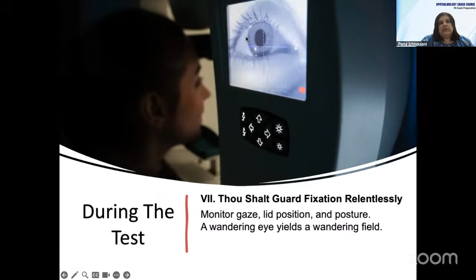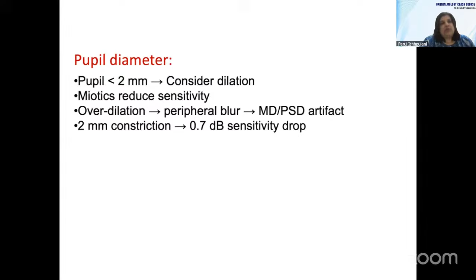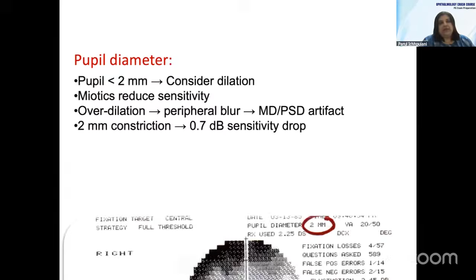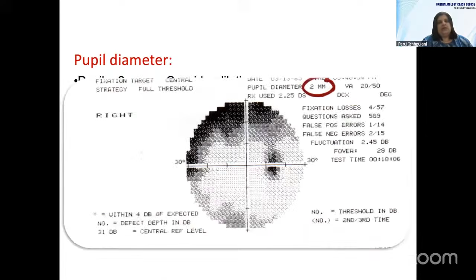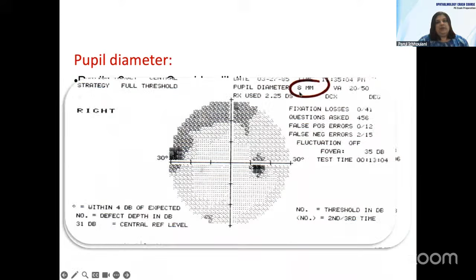Pupil diameter: miotic as well as mydriatic pupils result in a wrong outcome. Miosis reduces the sensitivity, while overdilatation causes a peripheral blur and results in a global indices artifact. A 2 millimeter constriction would result in about a 0.7 decibel sensitivity drop. So if the patient is on pilocarpine, that should be stopped a week prior, and then the test should be carried out. Here we see a very small pupil resulting in an artifact. And here we have another very largely dilated pupil, 8 millimeters, and again we have a peripheral artifact. So always look at the pupil size.